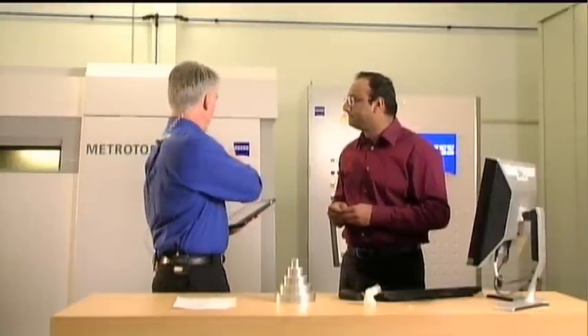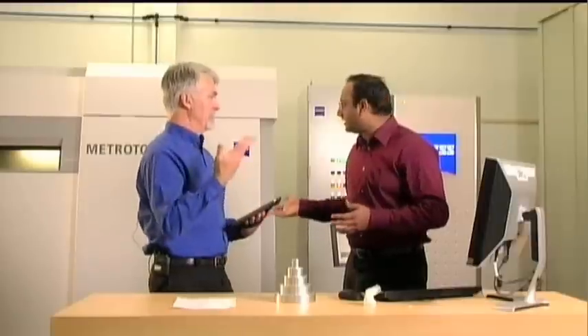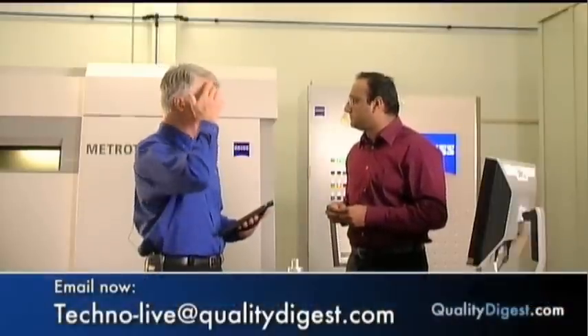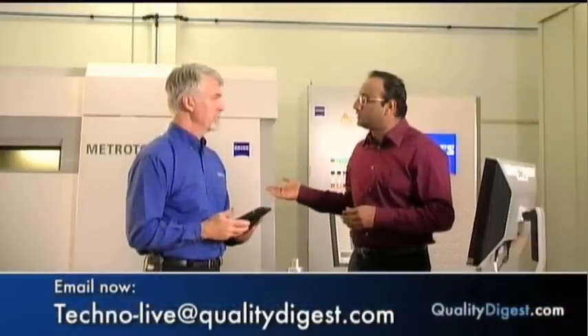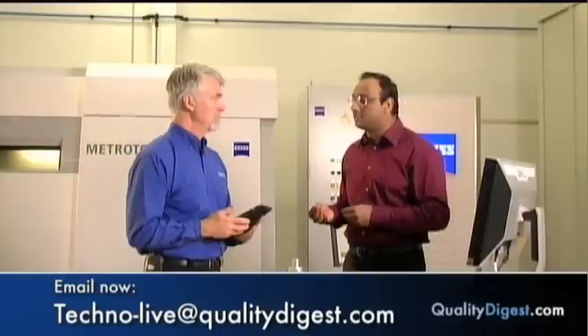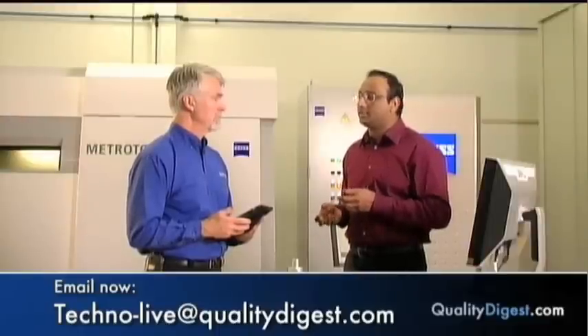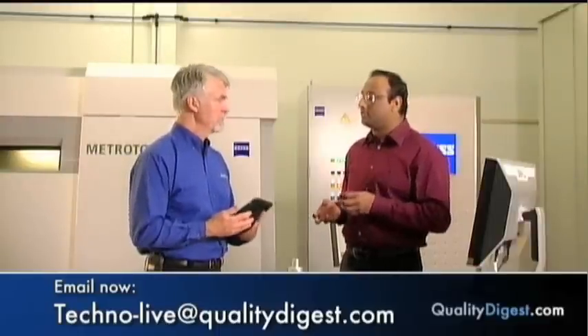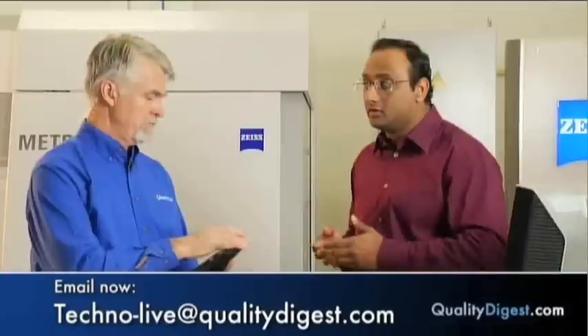We're standing right next to it, and there's no clearance area you have to worry about. The material that we use to generate X-rays is tungsten. Unlike some other elements, tungsten does not decay over a period of time, so there is no residual radiation left in the atmosphere. As soon as I turn the X-rays off, I can open the door and there is no radiation leakage.